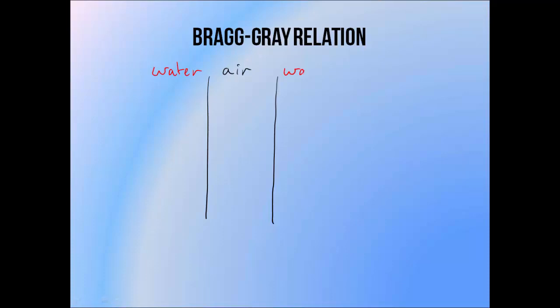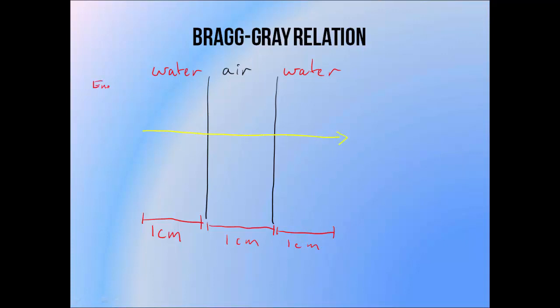Here we have a secondary electron crossing our ionisation chamber. It moves through a centimetre of water above the chamber, through our centimetre thick chamber, and a centimetre through the water behind the chamber. Let's assume for the moment that the electron loses energy steadily as it travels. The rate depends on the material, so here we'll say that it loses 1 MeV per centimetre in water, and 0.5 MeV per centimetre in air. It makes sense that it would lose less energy per distance travelled in air, since there are fewer things for the electrons to hit. And if we know how far this electron is travelling through each medium and the rate at which it loses energy per distance travelled, we can work out how much energy the electron is losing in each of these three areas.